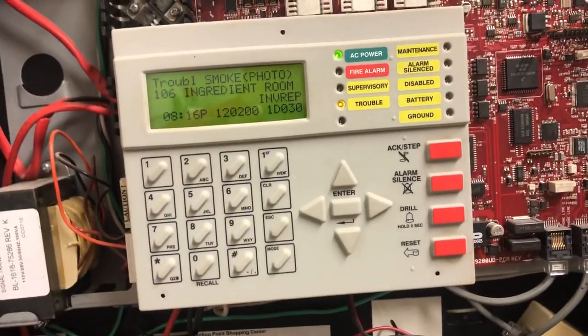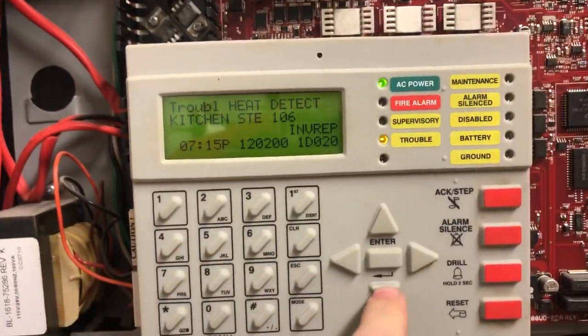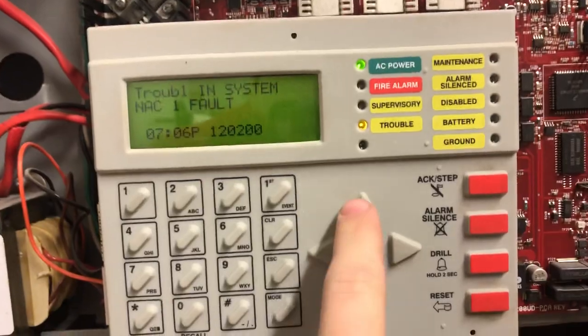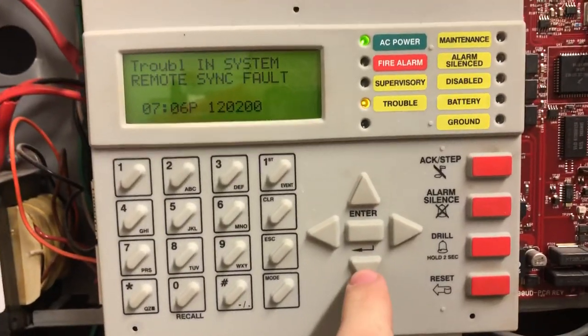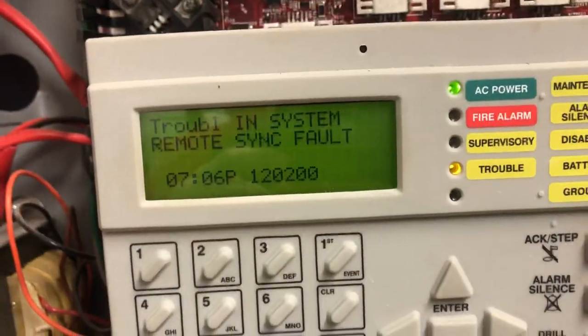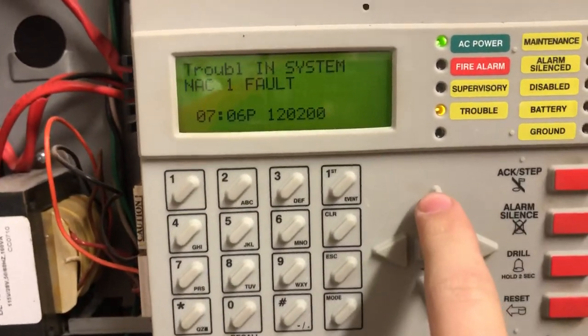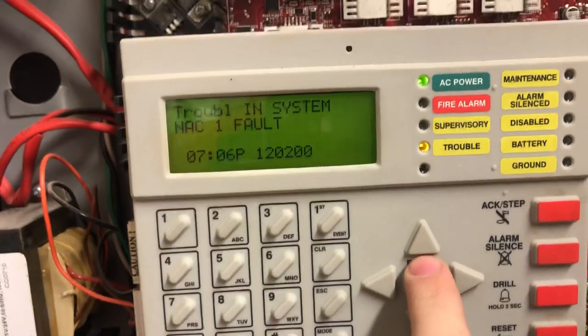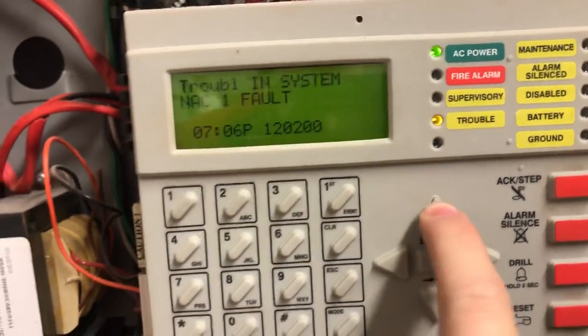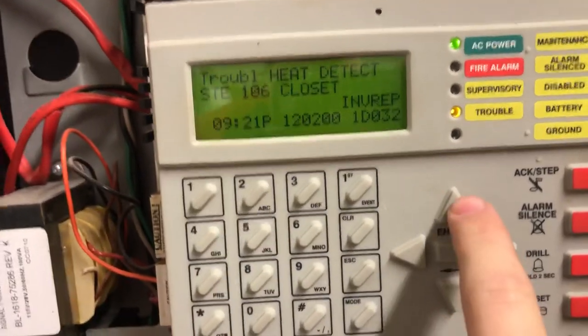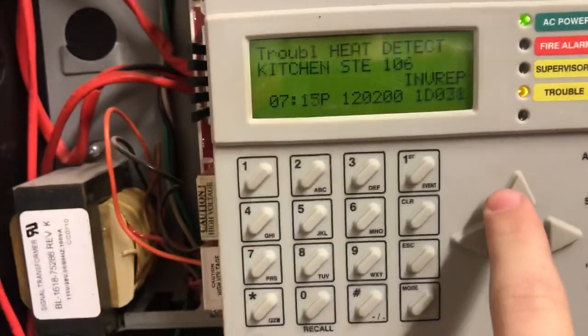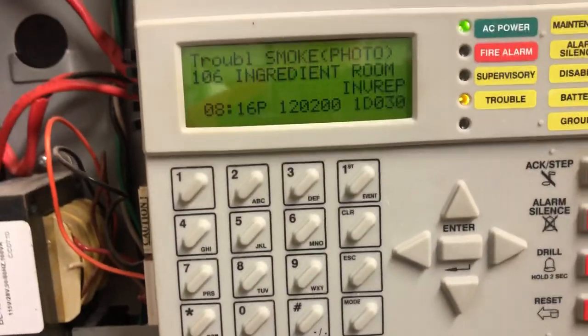I've been in the process of removing smoke heads, smoke and heat detectors, so I'm going to scroll through here and you'll be able to see the troubles in the system. Our first trouble is remote sync fault, then we have NAC4 and NAC1, which is the order in which I disconnected those NAC circuits. Then I've got a heat detector, heat detector, heat detector, and a smoke detector.